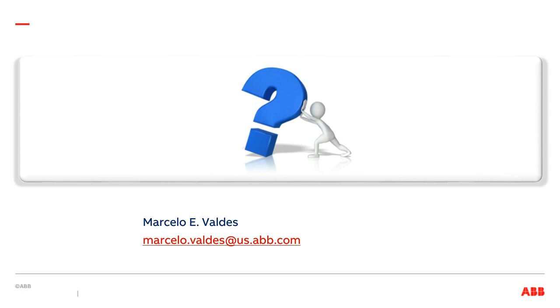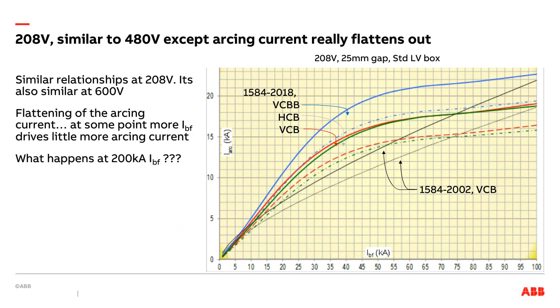Okay, sure. That's a very good question. Let me go back. It all comes down to this chart. Your fuse, circuit breaker, fancy or complicated relay, anything that measures current reacts to this current. It does not react to this current. This current is a theoretical value of interest only to people that do short circuit calculations and people that design circuit breakers and test them in laboratories. The only value that matters is the real value that happens in the real world. 99.9% of all faults are arcing. People argue how many of them are actually ground faults or start as ground faults. But as far as arc flash calculations, the assumption is they're all three-phase and they're arcing, which means this is the value of current that matters.